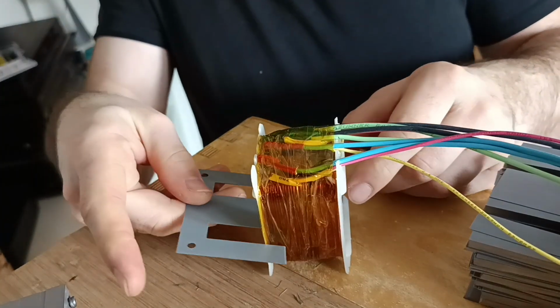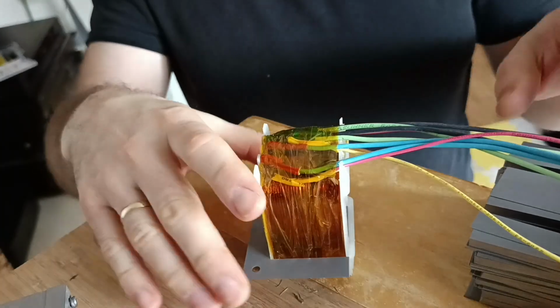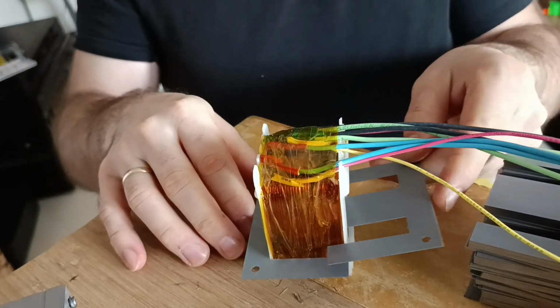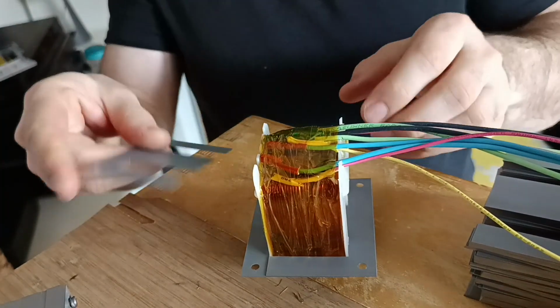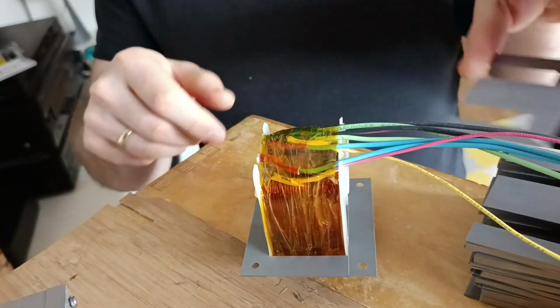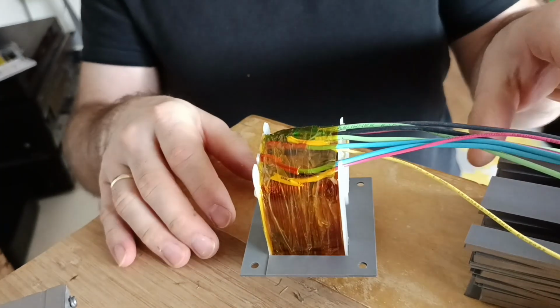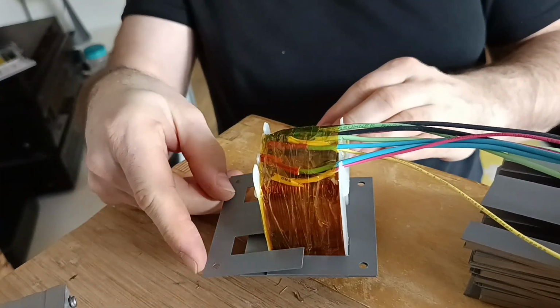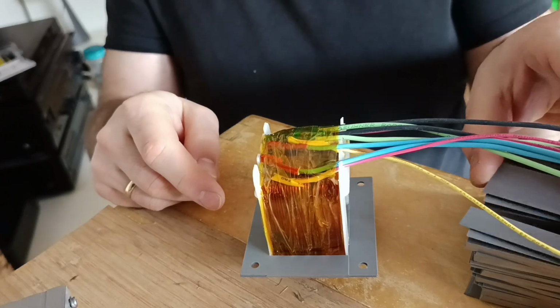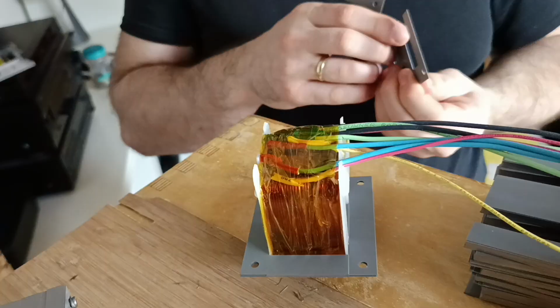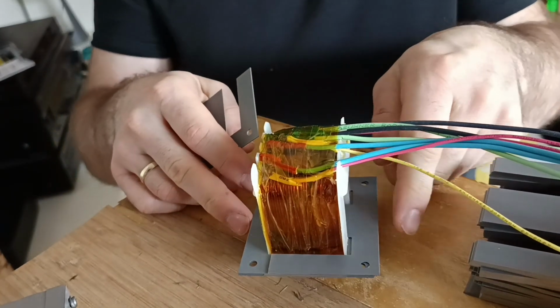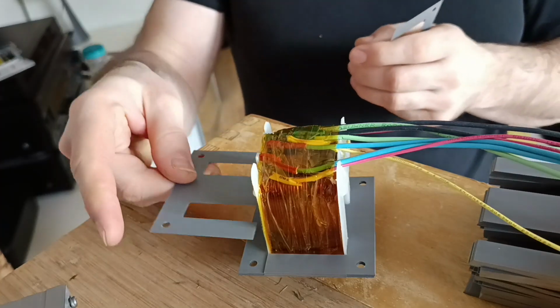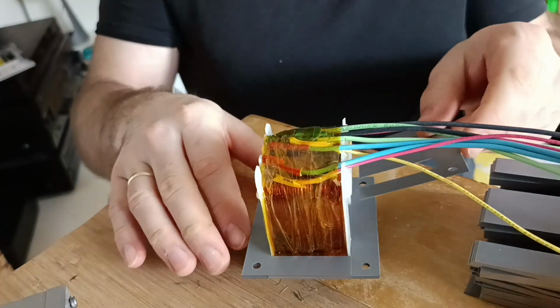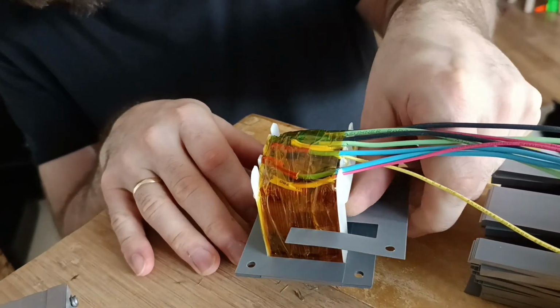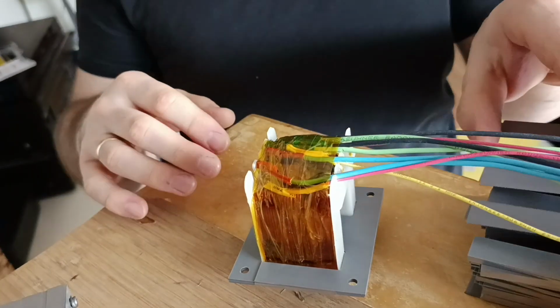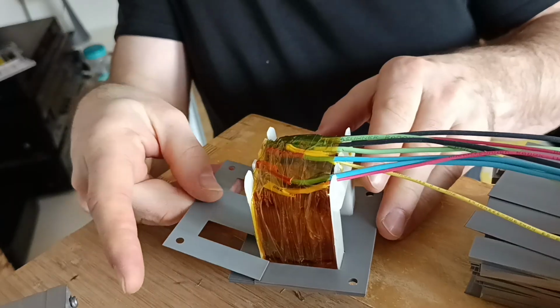For power transformers and push-pull transformers, we first assemble all the E laminations - one E lamination from one side, the other E lamination from the other side. You have to be careful when assembling this way to make sure you don't take two laminations at the same time, since that will make a gap which is difficult to fix - you'd need to add two I laminations to make it work, but it just becomes messy after that.